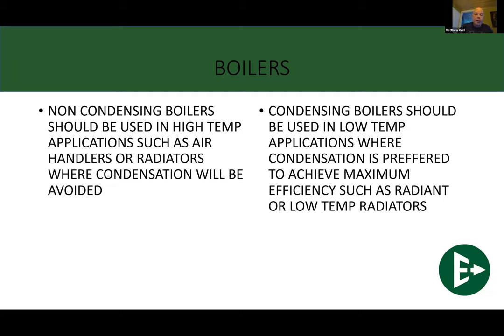Both of them have their place, I guess we'll say, in the market. Non-condensing boilers are great for high temperature applications, air handlers and radiators all day long. If that's what your system is made up primarily of, you can save some dough by going to a non-condensing, at least for now. The codes are going to be changing soon, if not already, for a couple of provinces out there that already require a modulating condensing boiler. Condensing boilers can be used much more effectively in low temperature applications. Usually it refers to low temperature radiators or radiant in-floor heating. So this is kind of the big two applications.